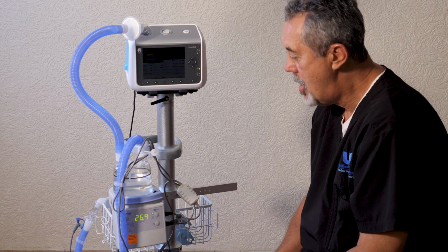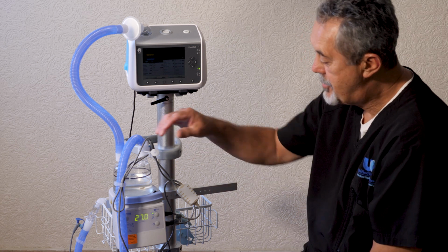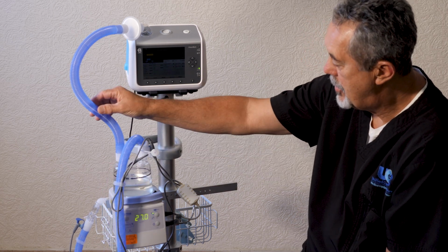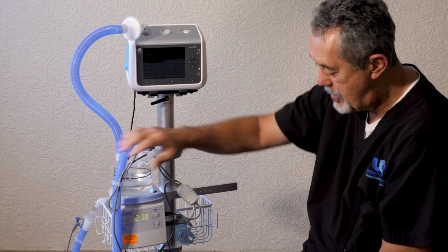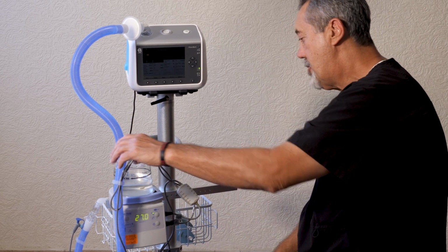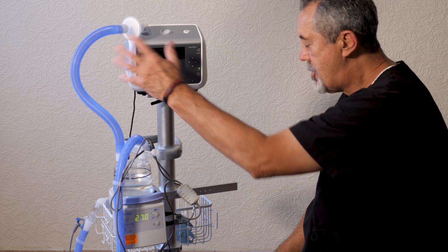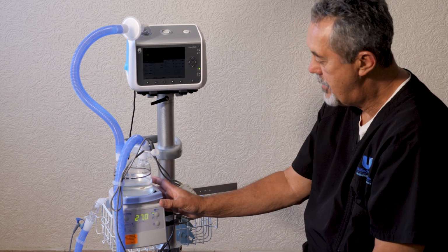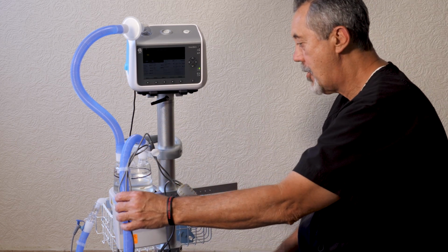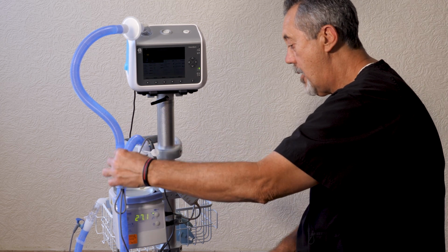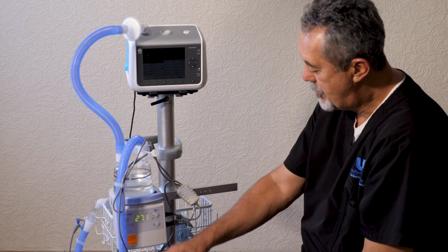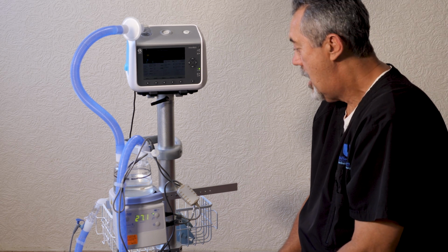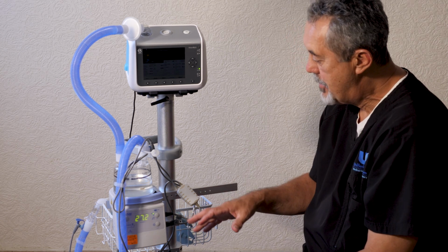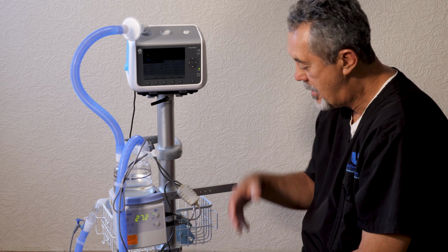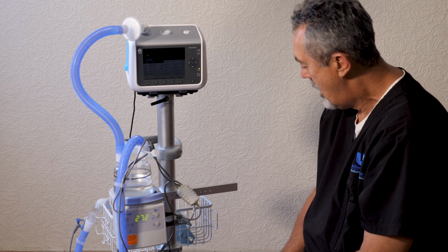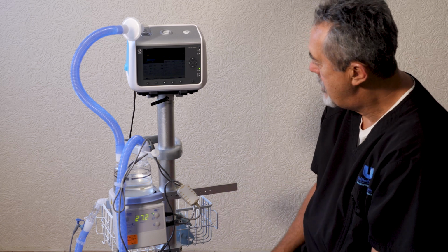Now, one thing you might want to note is that if you just happen to change the circuit, because typically these circuits with the pediatrics, we do mostly pediatrics, these circuits are changed on a weekly basis. So let's say you just change your circuit and now you have an alarm with the humidifier. Well, most likely it's the circuit. The circuit has a heated wire that runs through it, and that wire sometimes can go bad, even if it's straight from the factory. So if that happens, then change the circuit and try it again. If that doesn't work, then call the medical equipment provider. Okay, so that's how you troubleshoot the humidifier.